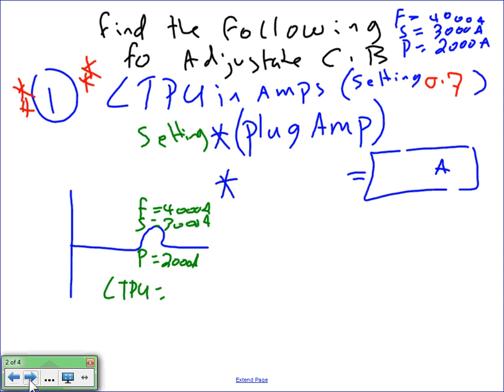Everybody's with me? I have a circuit breaker. I bought it. The frame size is 4,000. The sensor size is 3,000, and the plug that I'm plugging in is 2,000, right? Imagine if they come up in this way. And I need you guys to find the following: long time pickup. And I decided single-handedly, Mr. Kurdi, to put the setting for the long time pickup like we did in SKM. The setting was set at 0.7. I'm setting this circuit breaker at 0.7. And I need you to find the amp setting for this circuit breaker. Cool?